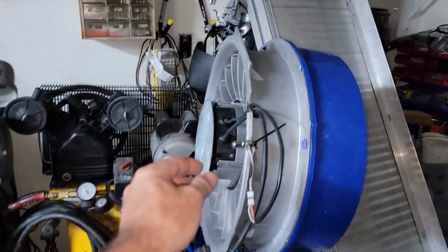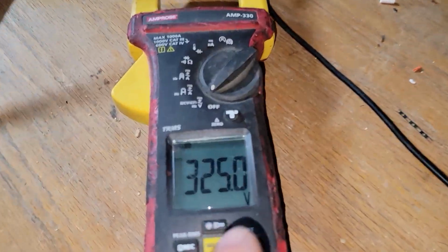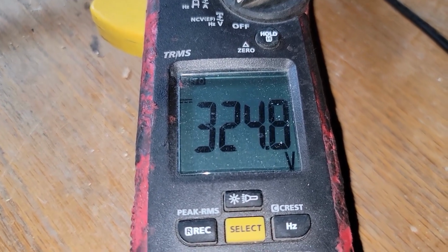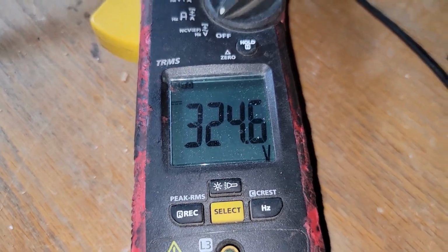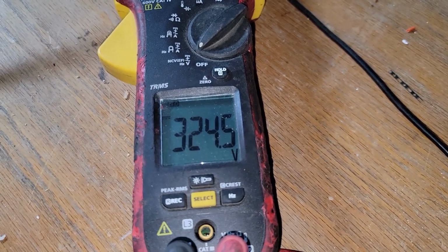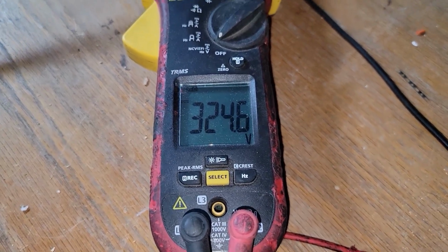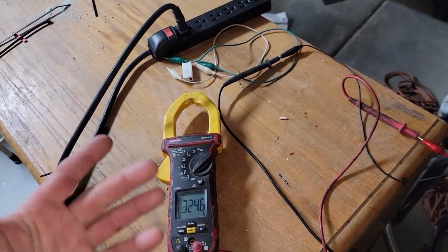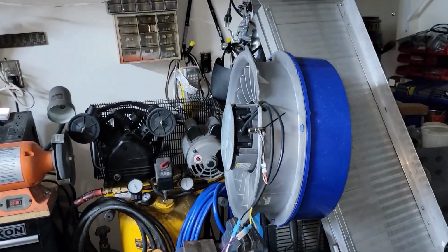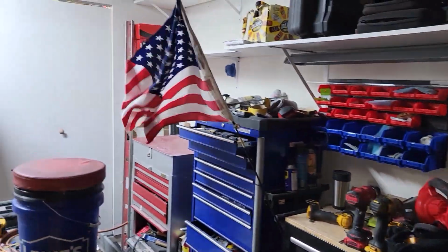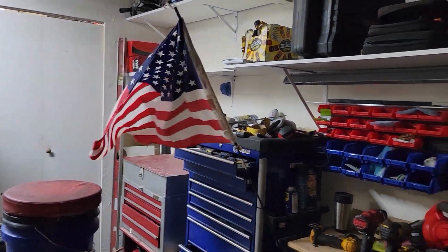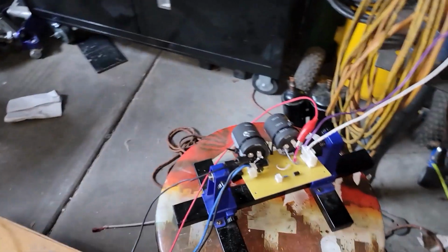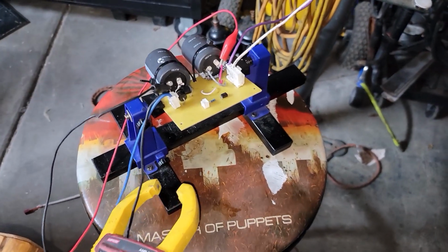It just turned on there because it has a little delay and then it runs. So you can see my secondary voltage is almost 330. If I don't have the fan running, it's about 330. You're always going to get a little bit of sag when you are consuming power, but once I crank it up, it actually sags a lot, and then it will hit a low voltage and cut out. So for your viewing pleasure, we put the old Glory over there, about 8 feet away, so you can see. Put this amp meter back on here too.